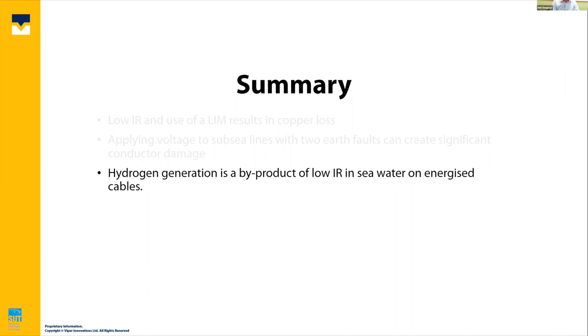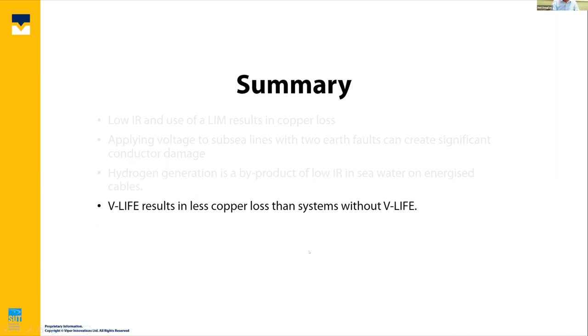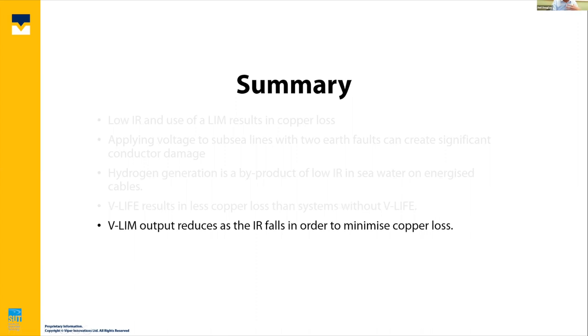I think you've hopefully seen from this presentation that the hydrogen is actually a byproduct and an indicator of low insulation resistance. So if you see or detect hydrogen coming out at the top of your umbilical, chances are it's as a result of low insulation resistance within the umbilical. If you apply V-life, it results in less copper loss and therefore will extend your system life. And then finally, with that V-LIM output, we reduce the output as the insulation resistance falls, so that under normal monitoring conditions we minimize this copper loss.